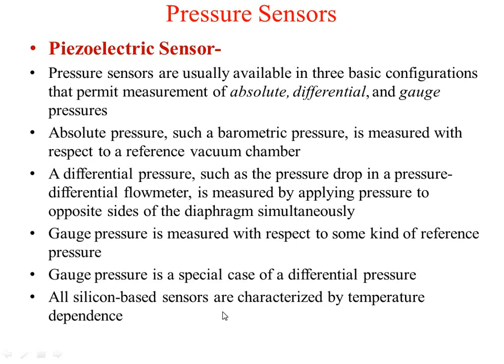So gauge pressure is a special case of differential pressure, and all the silicon based sensors are characterized by the temperature dependence. So you need a temperature compensation techniques in such kind of silicon based sensors. So in many applications, simple yet temperature coefficient compensation is required by adding a sensor, either series or a parallel temperature stable resistor, so that will provide you the compensation for the temperature.